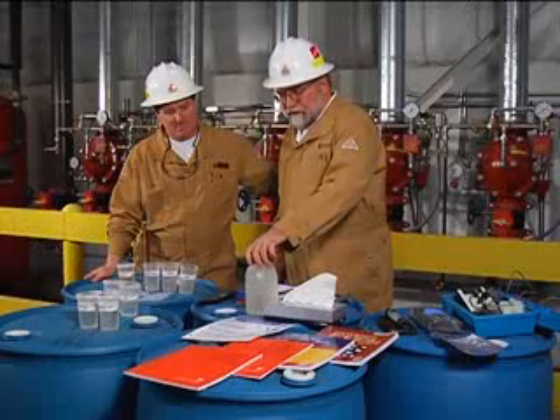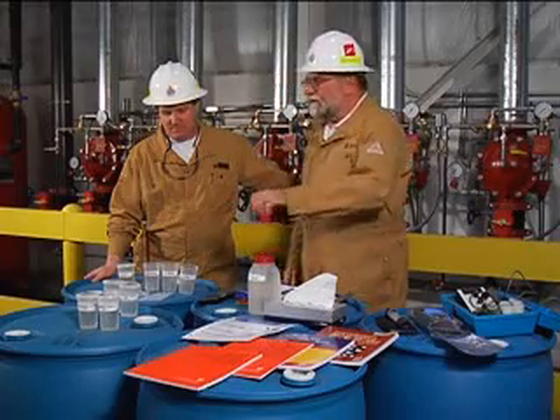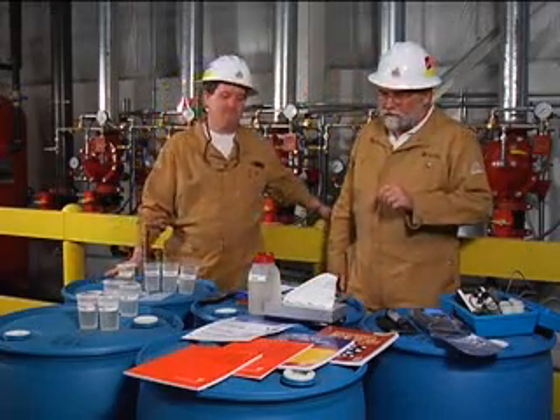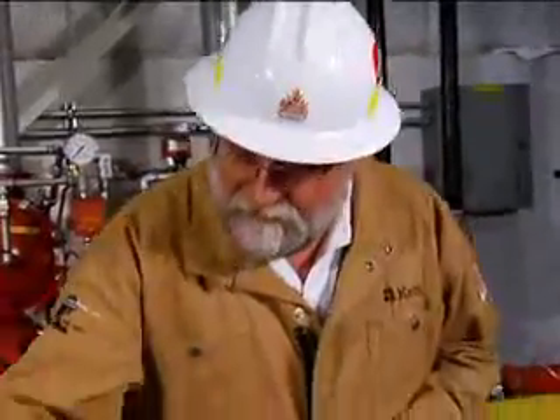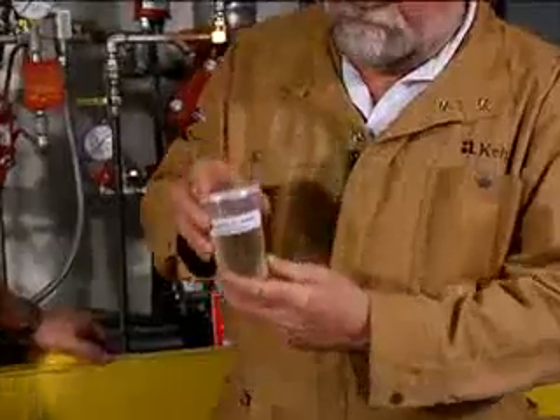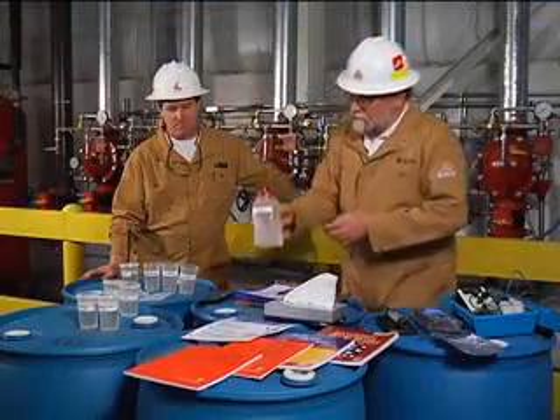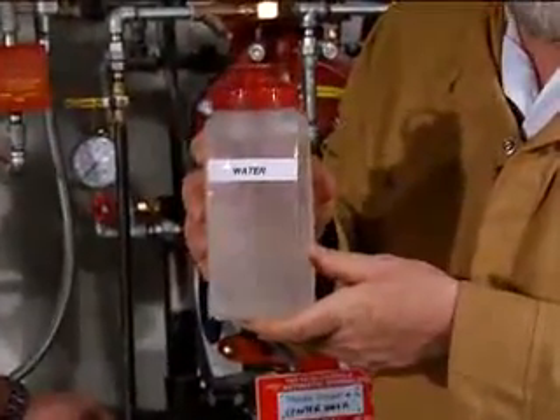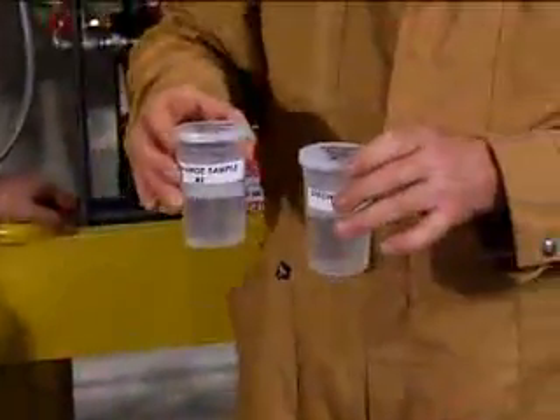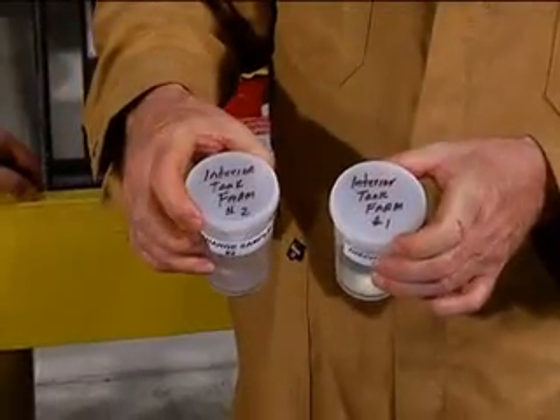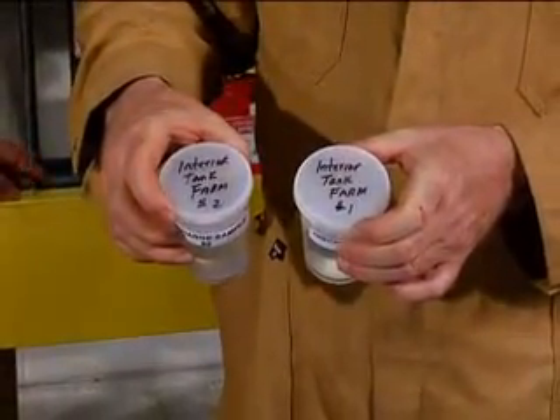Commission testing the Ansul bladder tank. We've completed doing the discharge test through the hose monsters and the play pipes at the outside of the facility, and we're now ready to test for the concentration percentages of those discharge samples that we took. What we've taken is samples of the concentrate from the foam bladder tank. We've taken a sample of the fire water that's used to support the design of the system. From the discharge test we did yesterday, we have the interior tank farm foam discharge samples that we collected, sample number 1 and sample number 2.